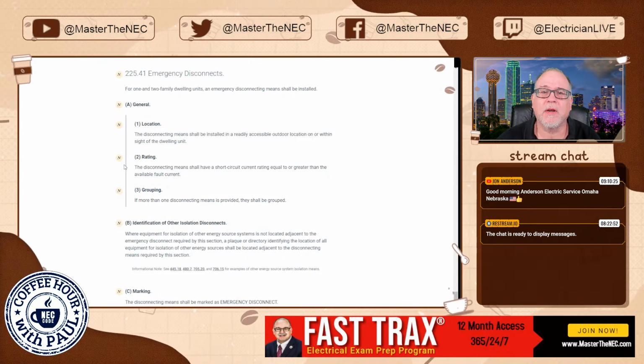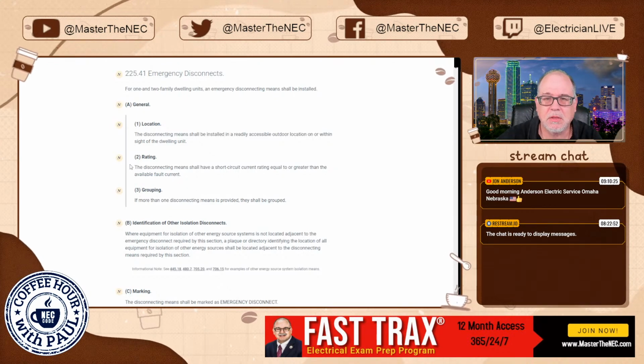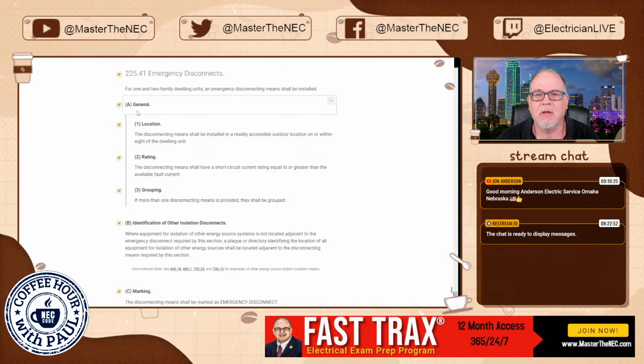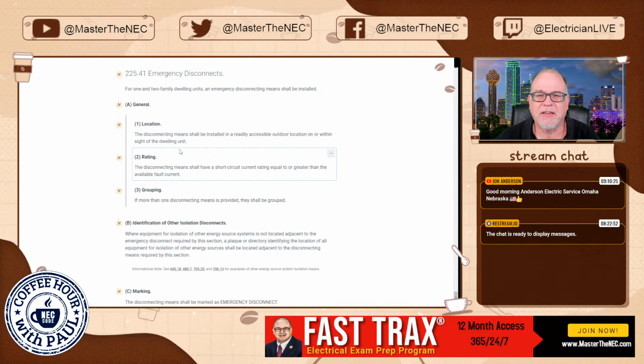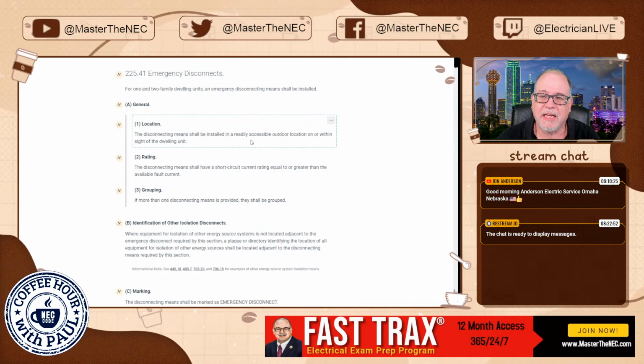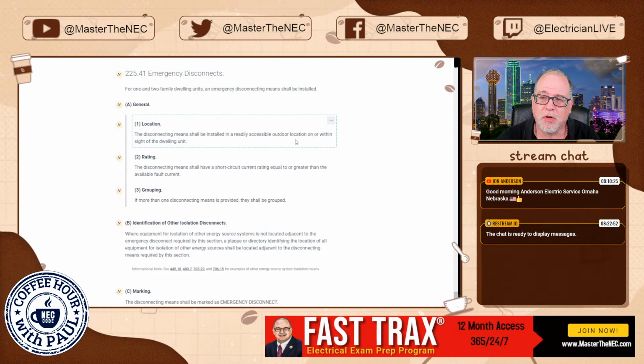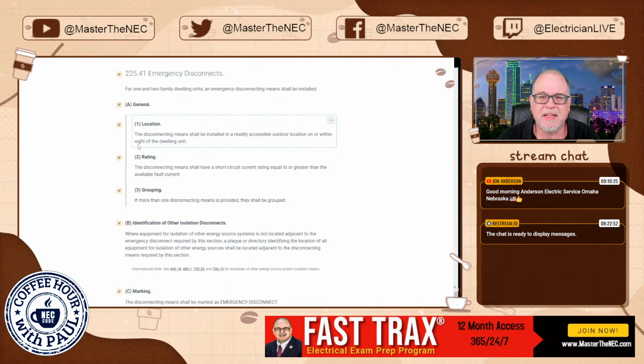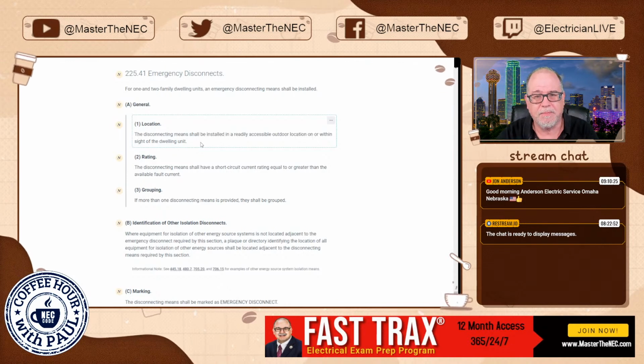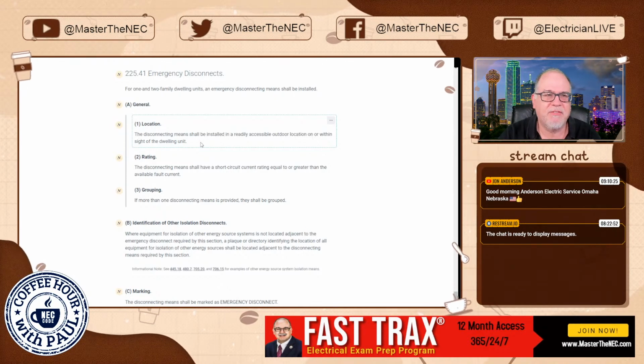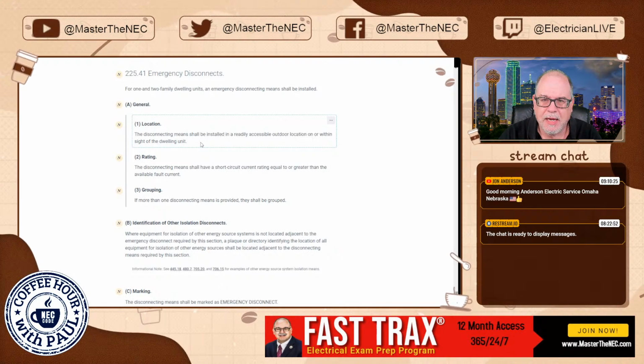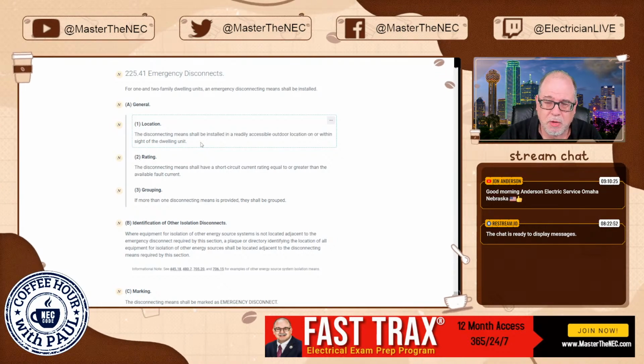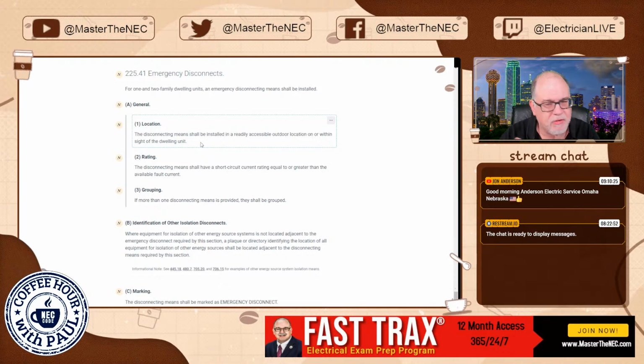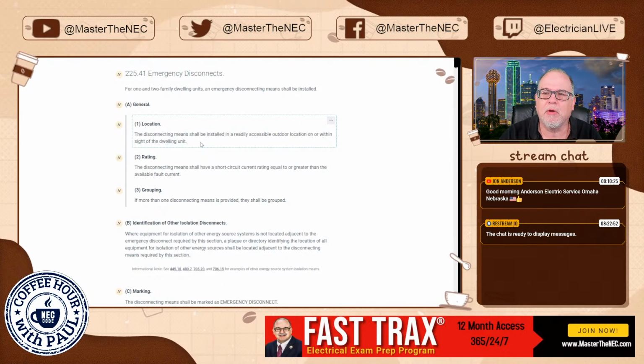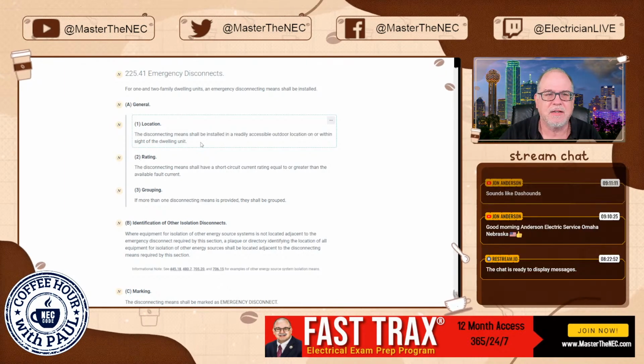So 225.41, I'm gonna yell at my dogs. Emergency disconnects. General. Location. The disconnecting means shall be installed in a readily accessible outdoor location on or within sight of the dwelling unit.